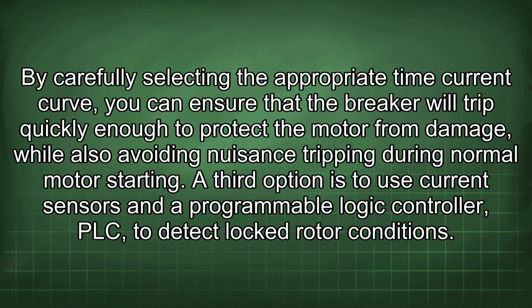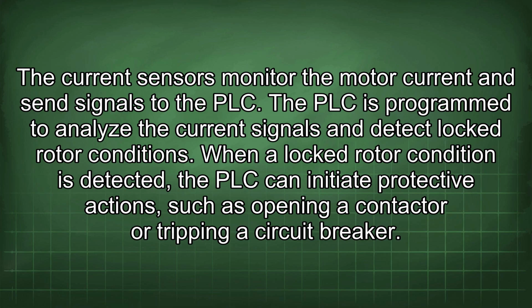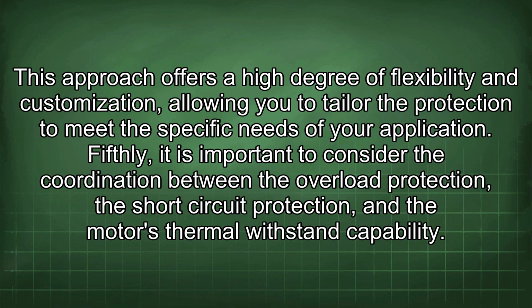A third option is to use current sensors and the programmable logic controller, PLC, to detect locked rotor conditions. The current sensors monitor the motor current and send signals to the PLC. The PLC is programmed to analyze the current signals and detect locked rotor conditions. When a locked rotor condition is detected, the PLC can initiate protective actions, such as opening a contactor or tripping a circuit breaker. This approach offers a high degree of flexibility and customization, allowing you to tailor the protection to meet the specific needs of your application.